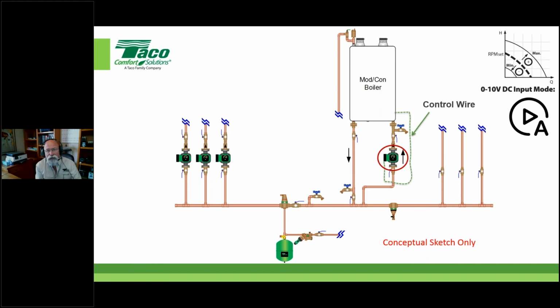The problem I see out there, especially with some competitor products that come packaged together, is there's an old saying: you can't go any lower than low. If you put a circulator on there that has 0 to 10 but is physically too big for the job it's being asked to do, it just sits there on low speed. It can't go any lower, and therefore it cannot widen that delta T any more than at low speed. A lot of you know where I'm going with that, but maybe I should open it up for questions.